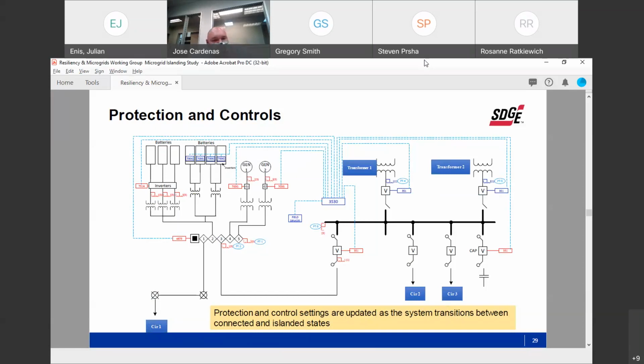Also, as Stephen had mentioned, and Devon did for the sync, we're getting voltage magnitude and angle from that point of common coupling fed back to our resources in the microgrid to sync up the voltage and angle for the grid. Then, like they mentioned, the microgrid will verify it's synced, and inside the substation, there's another sync that verifies that we are truly synced, and then sends the breaker command to close. Next slide here, please.